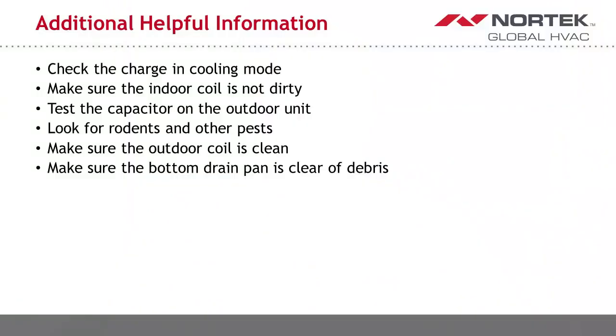The last thing I will tell you is always check the heat pump from the thermostat. What I mean by that is, I was always one that did it too. When I was out there, I'd use a jumper wire to control everything. And that's fine, you still can do that on your PM check. But the last thing you do before you leave is go to the thermostat and make sure the thermostat is turning the equipment on and turning the equipment off.